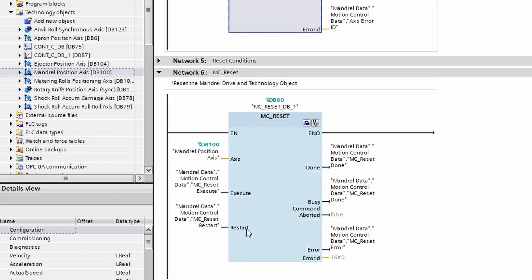So we have a little bit different outputs on this block versus the MC_Power. A big difference between the done and status bit is that the done bit is only true for one cycle after the function completes its operation.